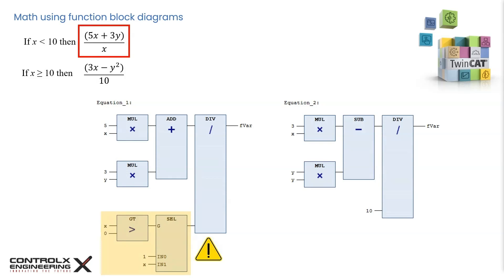If x is greater than 0, then the g input of the select operator is true, which results in its output being the variable at in1 input. Otherwise, if x equals 0, then g is false, and the output of the select operator is in0, which has been set to 1. Therefore, the division operator will never get a 0 as the divisor, thus preventing a PLC crash.